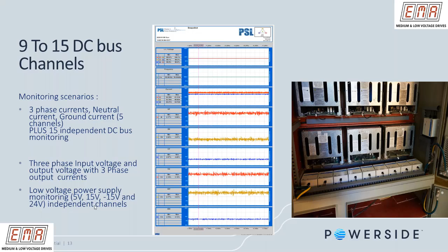They can receive snapshots, and snapshots are problems. When there's a problem, the drive scan will take a snapshot of the problem before it happens and send us all these 10 reports so we can look at it and determine what happened to the VFD. We can look at output current, output voltage as well, and all our low voltage power supplies, as I indicated earlier. This is a good example of a snapshot of a problem that happened on a drive scan.